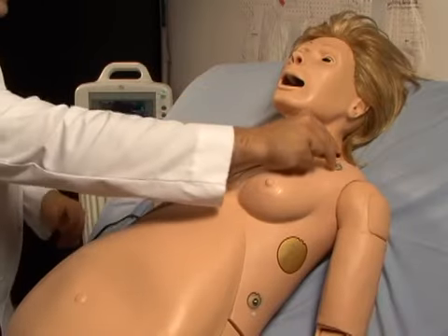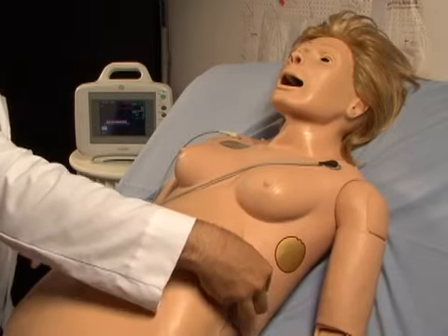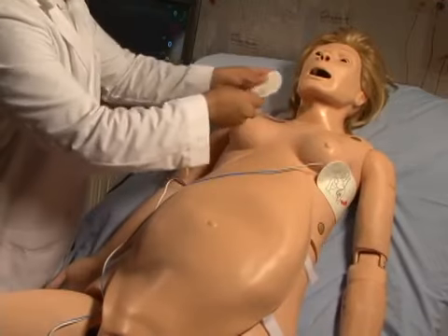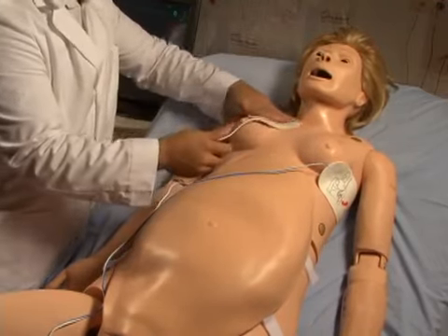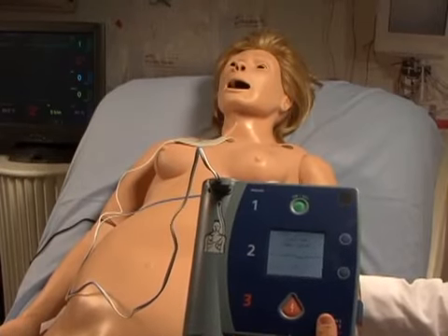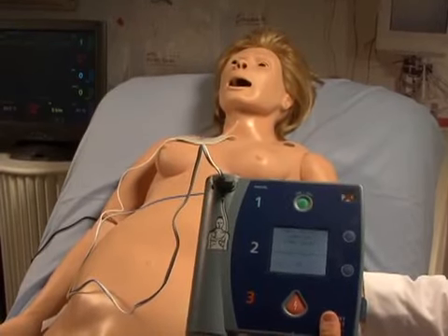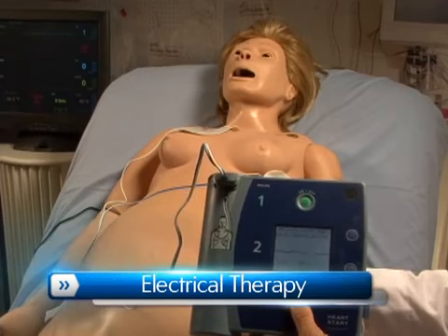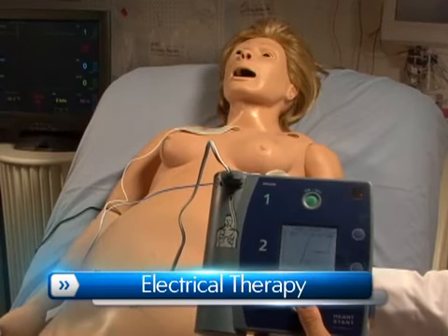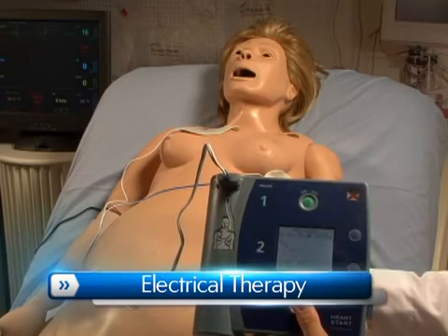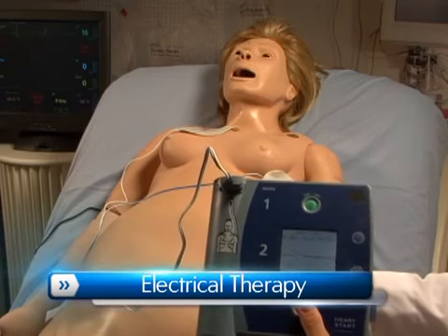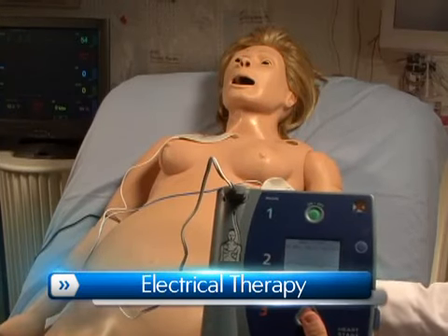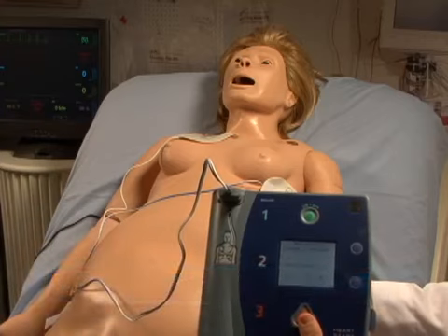Noelle's conductive skin sites allow the attachment of real electrodes and defibrillator pads. This feature permits the user to track cardiac rhythms and events with their own equipment, just like with a human patient. To add to this realism, Noelle can be shocked or paced with real energy for cardioversion, defibrillation, and pacing drills. An AED will display Noelle's ECG, analyze her cardiac rhythm, and advise action, a perfect addition to competency-based programs.